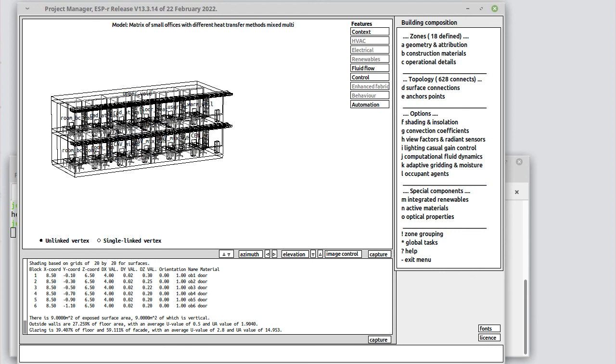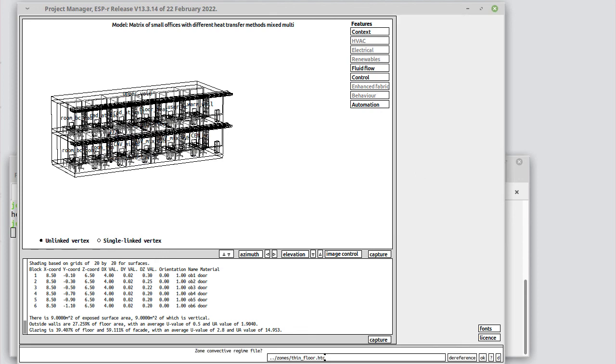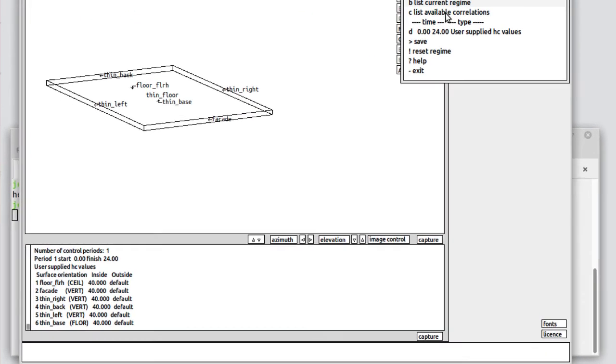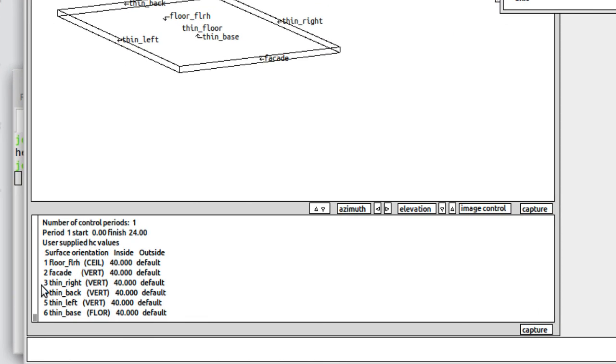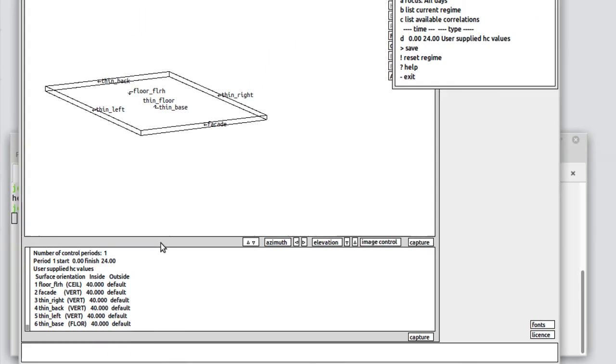In order to enable this kind of control, we've set convective heat transfer coefficients. If we look in here, we'll see that the thin floor has coefficients defined and it's user defined. The current regime sets one control period lasting the whole day and for each of the surfaces related to the floor, the inside heat transfer coefficient has been set to 40 and the far side uses the default.